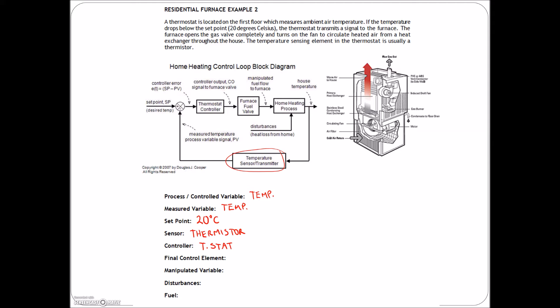In this case it's a natural gas furnace, so our final control element — depending on how you look at it — could be the gas valve or the blower motor, as there are multiple stages to furnaces. The manipulated variable is what we're changing. In this case we're manipulating gas flow by opening and closing that valve. If you're talking about the blower motor, then we're manipulating airflow through the ducts. The fuel: we're sending current to either the valve or the blower motor.